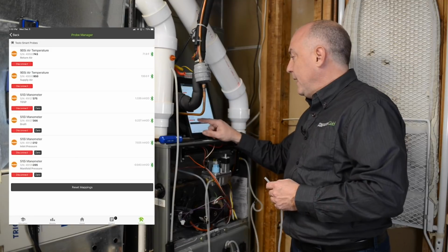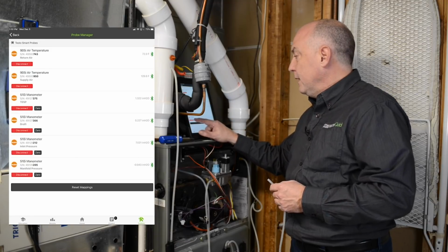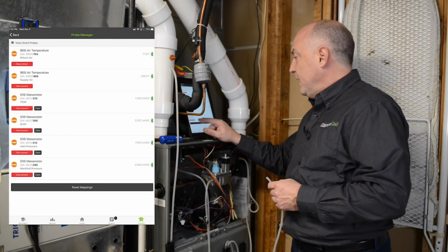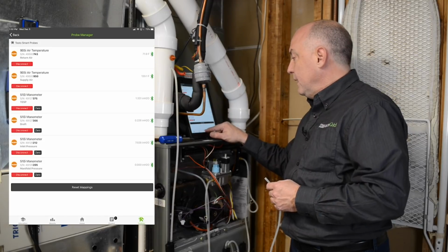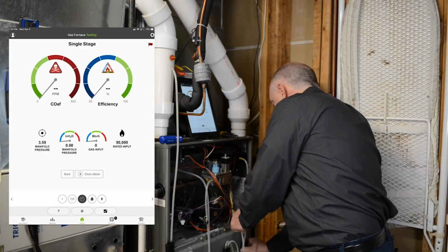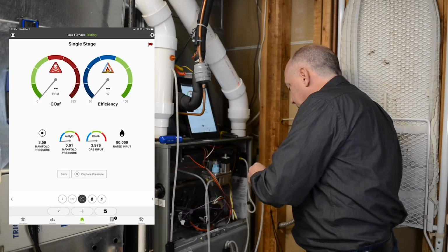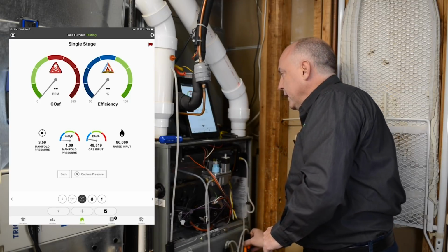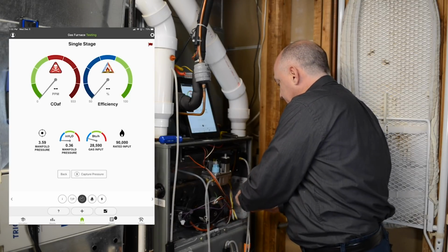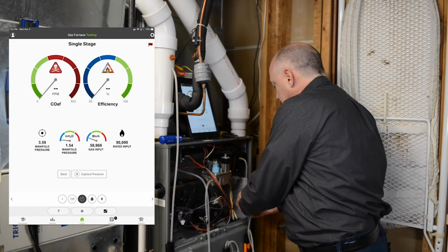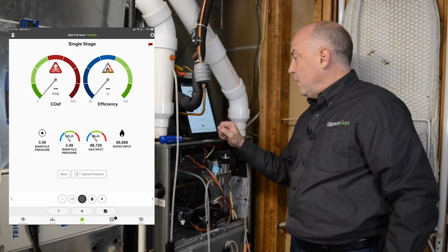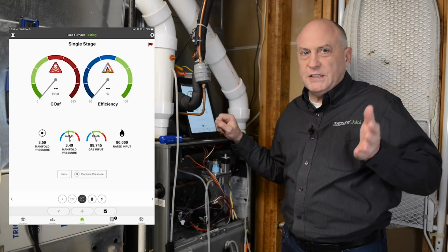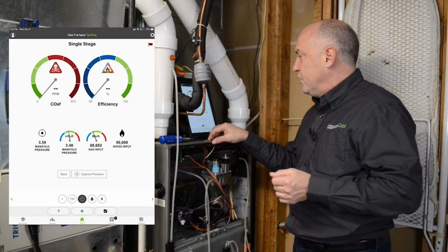So tap on the probe manager. Down at the bottom it says manifold pressure. I'm going to hit 0, hit dismiss, and now that probe is zeroed in. Now I'm going to go back down to the bottom here and reconnect this to the positive terminal, and I'm going to readjust my manifold pressure. So I've got to disconnect the hose here now, and I'm reading full pressure on my manifold ports. You can see I'm reading almost exactly the same as it was, 3.49 inches.